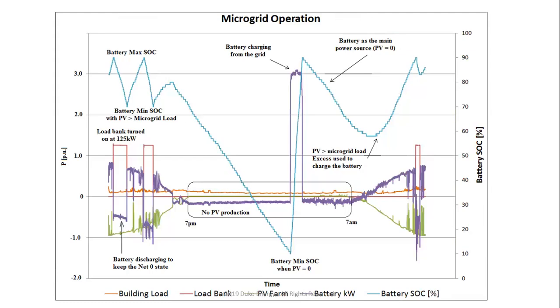And at that time, you can see how the battery starts discharging. When the battery hits 70%, we turn off that load bank. PV, which is green stuff, is greater than our orange, which is the building load. So we start charging the battery. So we go battery up and down until somewhere around 7 p.m. You can see how green goes to 0, which means there is no PV, right? At that time, battery becomes the sole source. So you can see how battery state of charge starts going from 80% and gets all the way down to 10%. That's pretty much in the middle of the night.